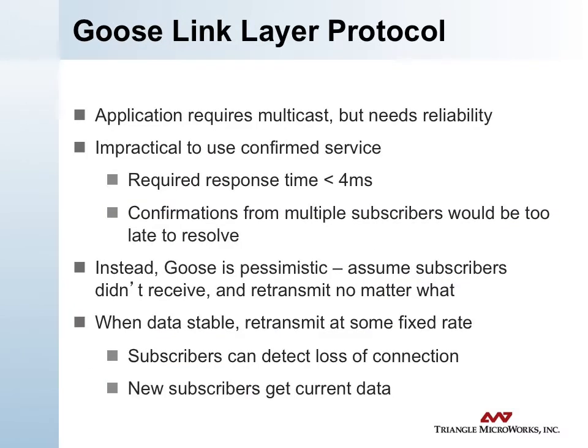Multicast is a problem in any protocol. When you have that kind of requirement, there's some inherent unreliability. They're typically unconfirmed. In our case, it was particularly impractical to use a confirmed service. We needed to have trip times and switch closure times in less than 4 milliseconds was our target requirement. And if you think about it, using most protocols, if you were going to do confirmation, then by the time you wait for the confirmation to come back from the receiver, it's too late to resend because you're already outside your 4 millisecond window. This is particularly a problem when you've got multiple subscribers coming to a single publisher, being able to resolve all of that.